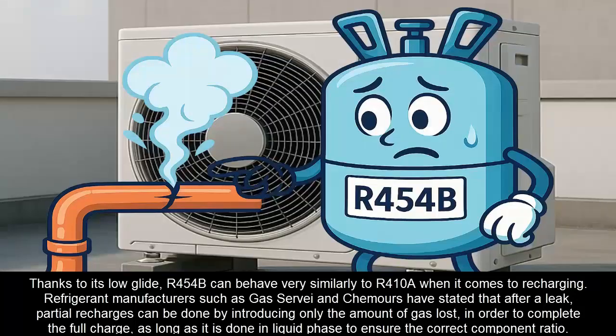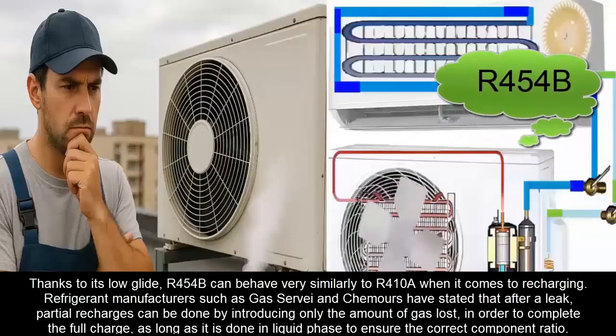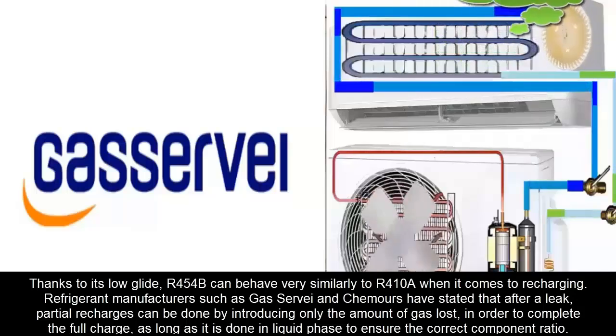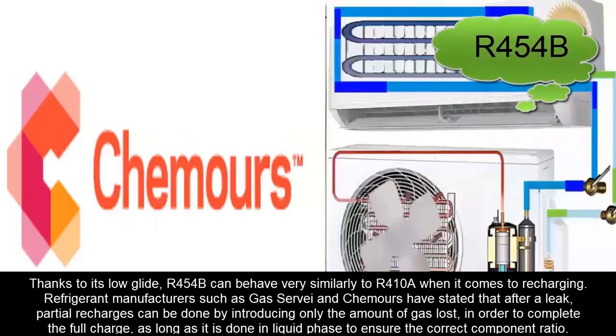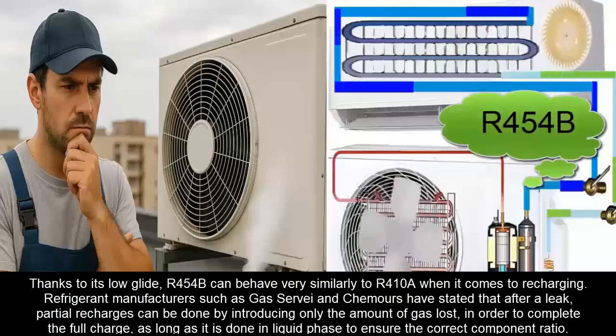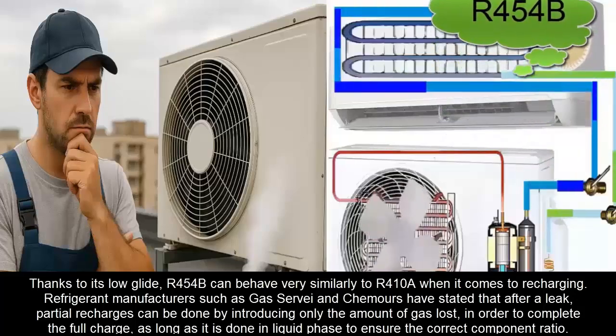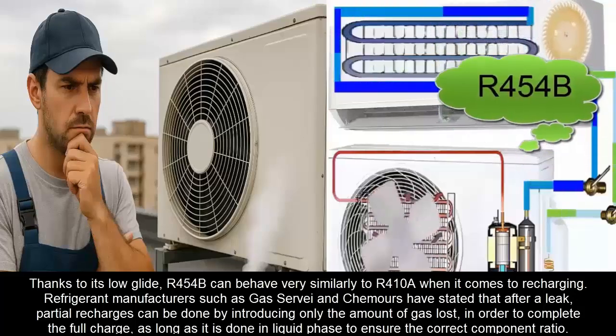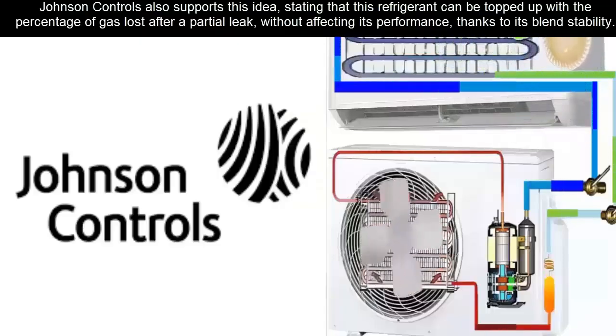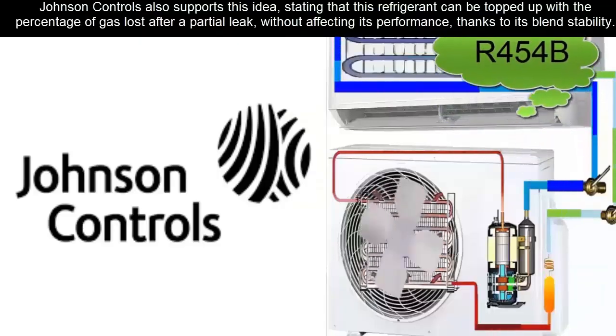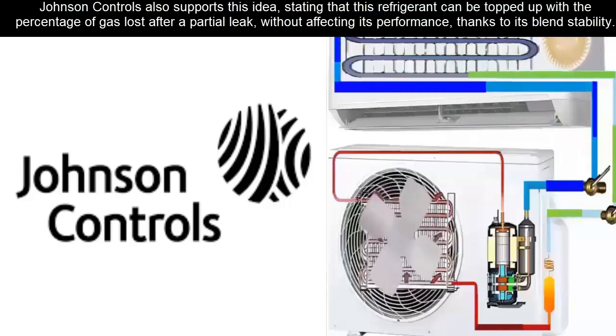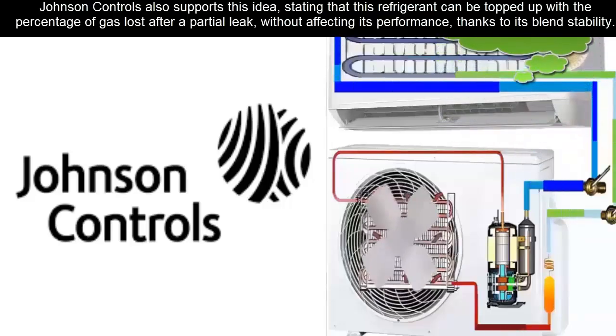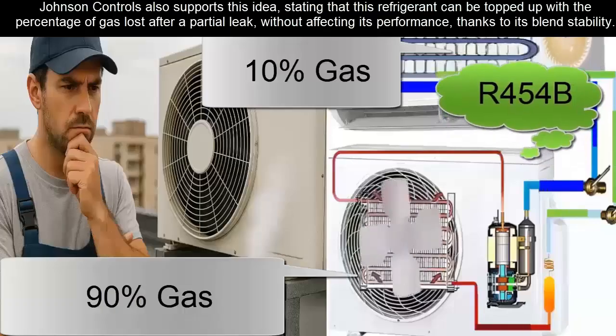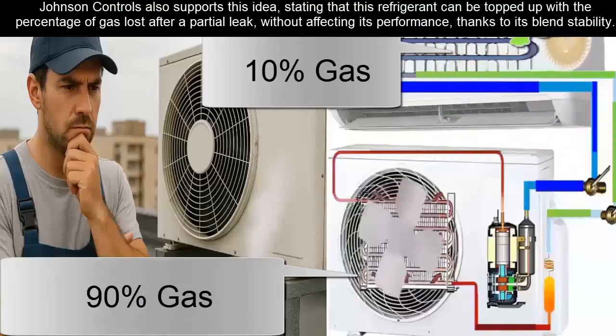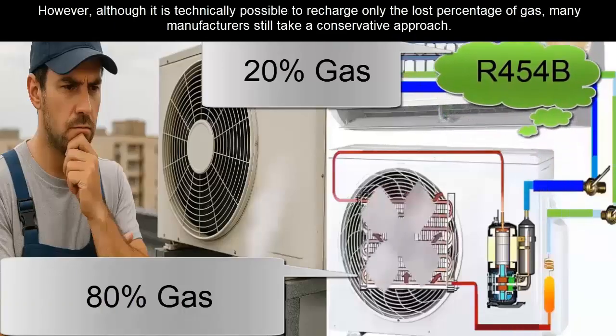Refrigerant manufacturers such as Gas Servei and Chemours have stated that after a leak, partial recharges can be done by introducing only the amount of gas lost in order to complete the full charge, as long as it is done in liquid phase to ensure the correct component ratio. Johnson Controls also supports this idea, stating that this refrigerant can be topped up with a percentage of gas lost after a partial leak without affecting its performance, thanks to its blend stability.